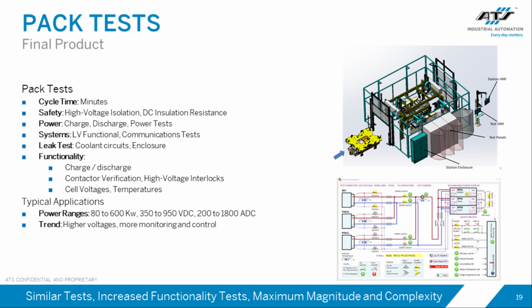Now in the power, the charge and discharge are typically the largest that we're going to see in our systems. One thing I might note here, you've got to be careful on discharges in terms of how you're doing that, in terms of what your facility can handle in terms of the electricity that's discharged. Most of these systems we like to have regenerative, so the power we're putting in, we're using when we take it back out. If you can't use all the power, then it needs to go somewhere.